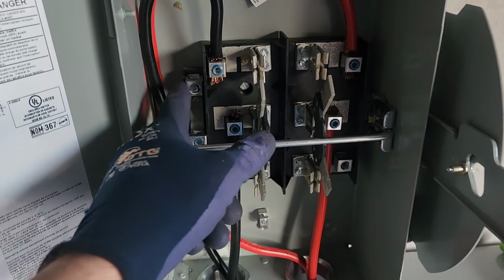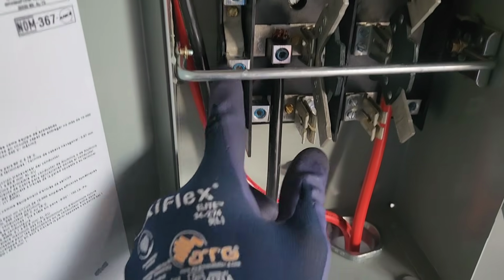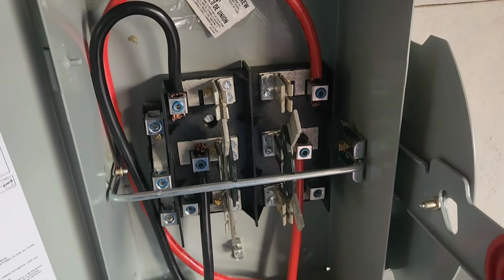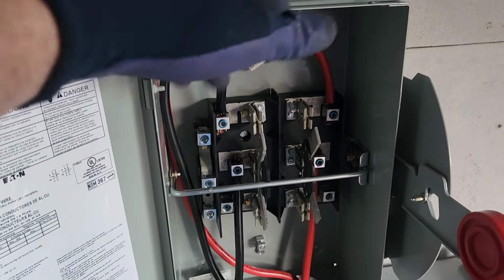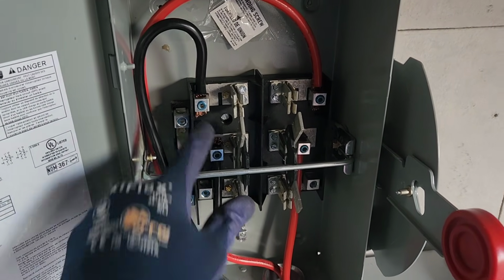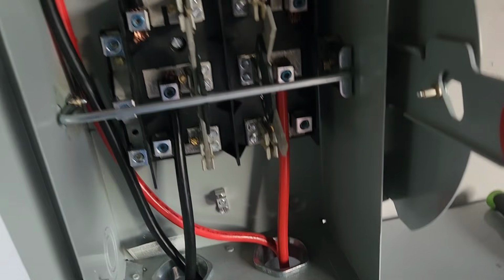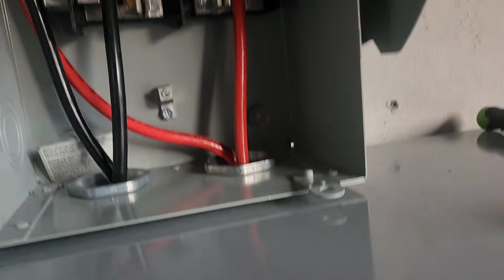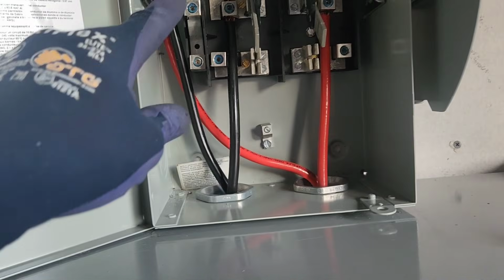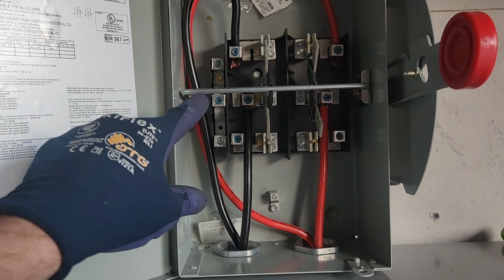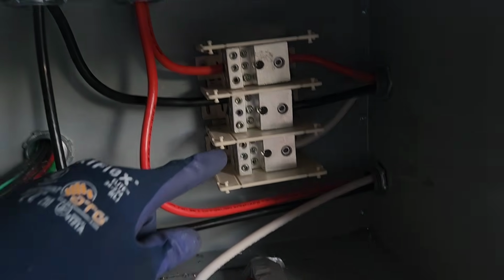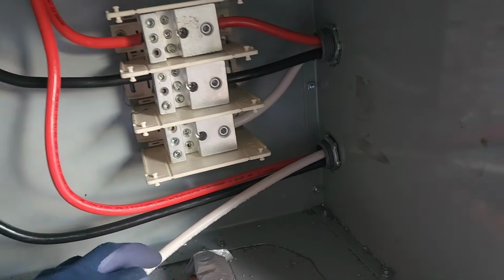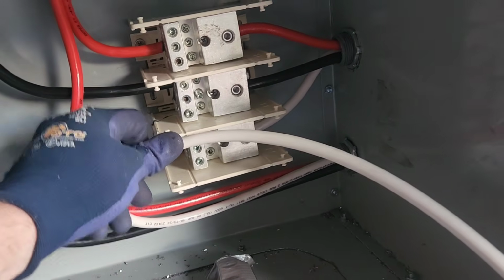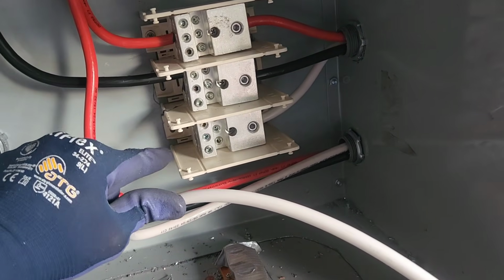Now I have a neutral bar here - that's just one big neutral bus bar. If you're feeding in from the top you can connect your neutral in there, or neutral in the bottom. Now I'm just going to feed my neutral - instead of connecting the neutral onto that bus bar, I'm just going to connect it onto this bus bar. So my neutral is really just coming in and then going back out.